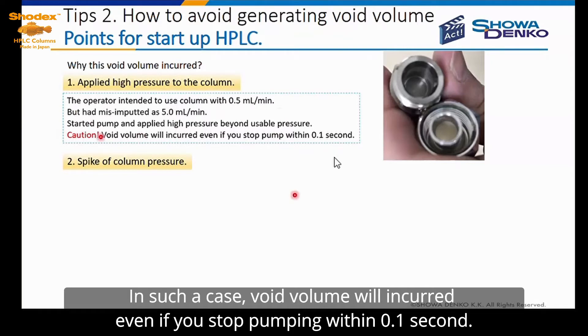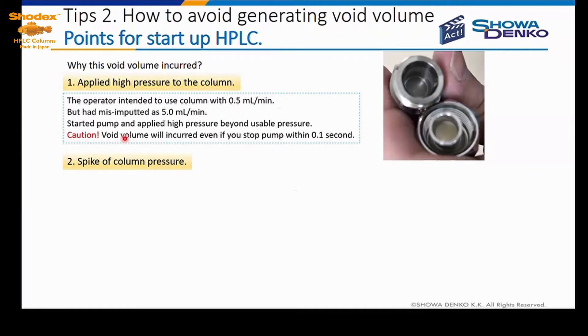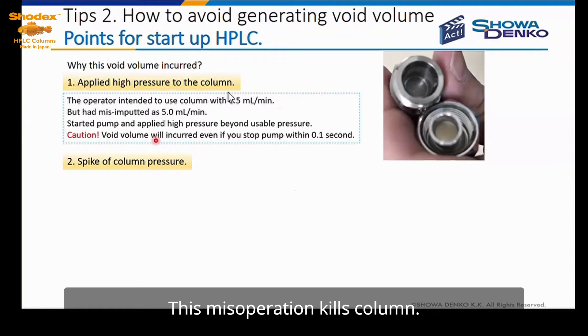In such a case, void volume will increase even if you stop pumping within 0.1 seconds. So this mis-operation kills the column.